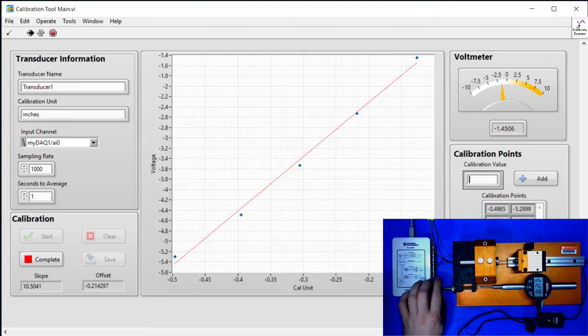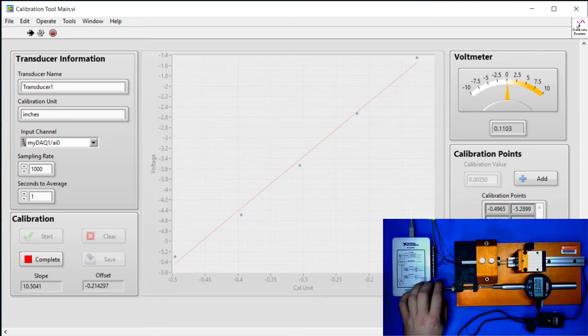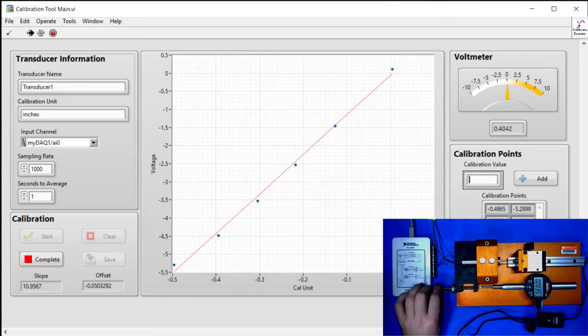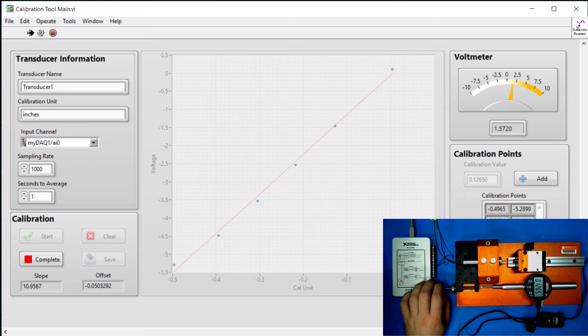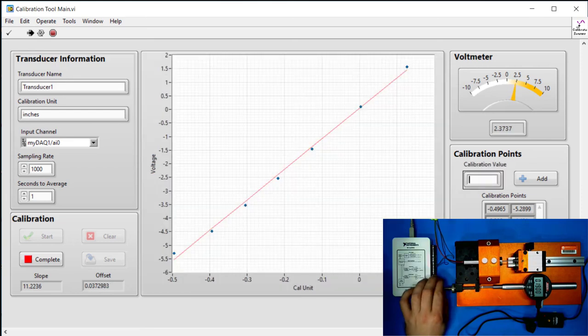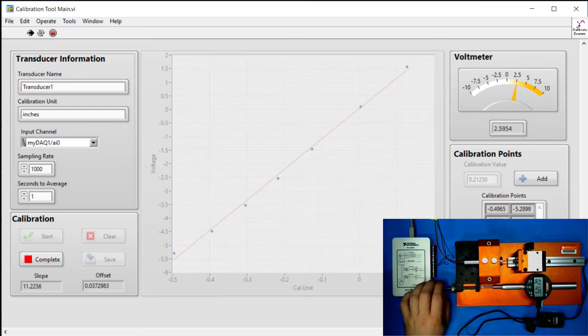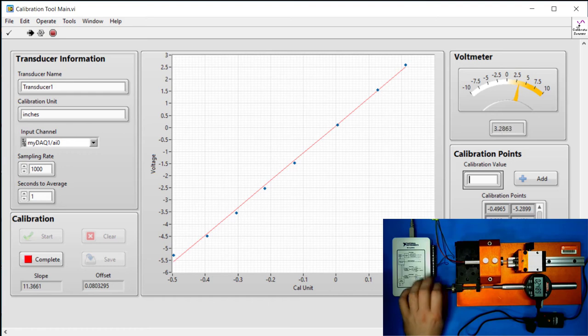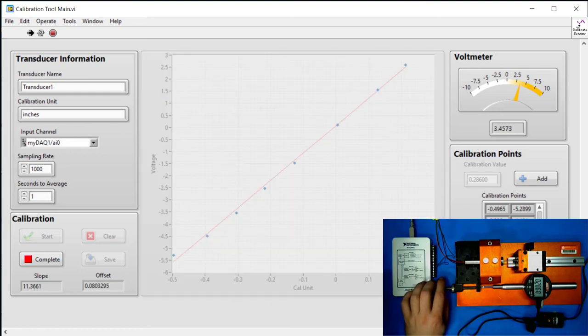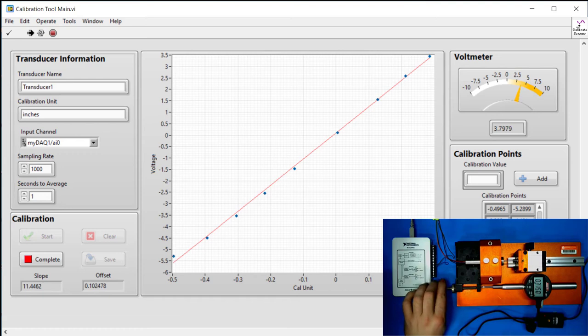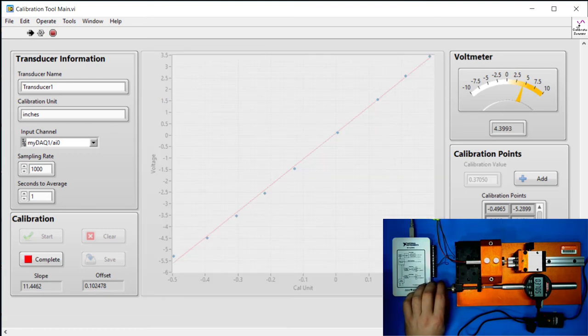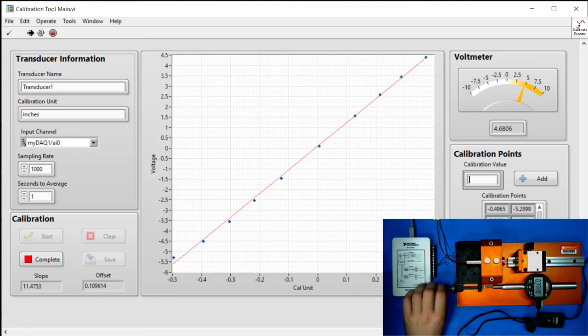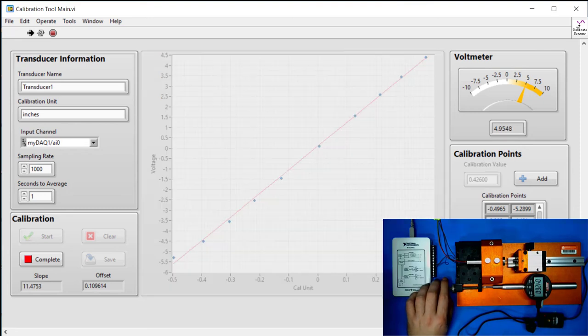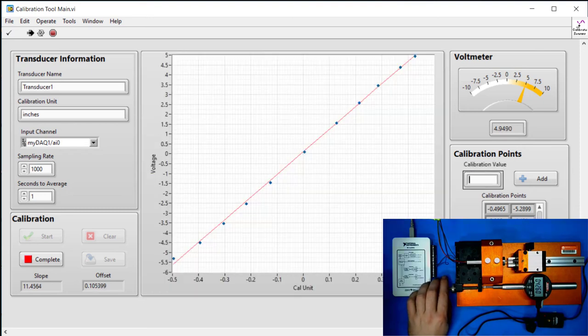We're going to go relatively coarse for purposes of the video. But as you can see, you can take all of these points in maybe a minute, or if you're taking a very dense point sampling, maybe every 2 minutes. So it's much quicker than calibrating transducers any other way. So we're going to take a few more on the way up. As you can see, it's building the calibration curve in real time for us.